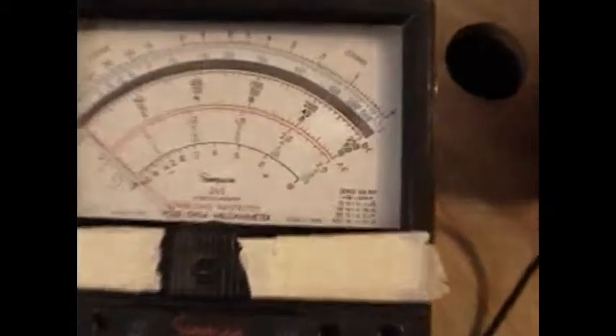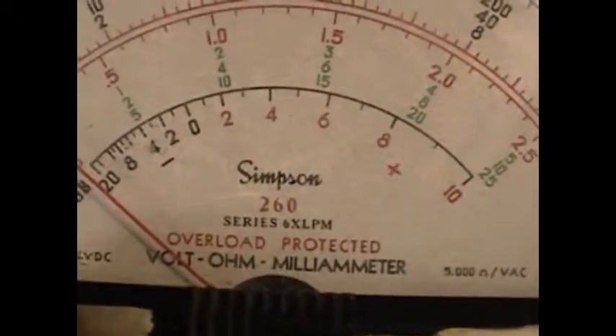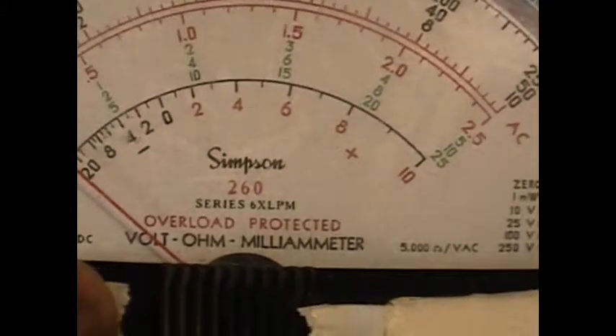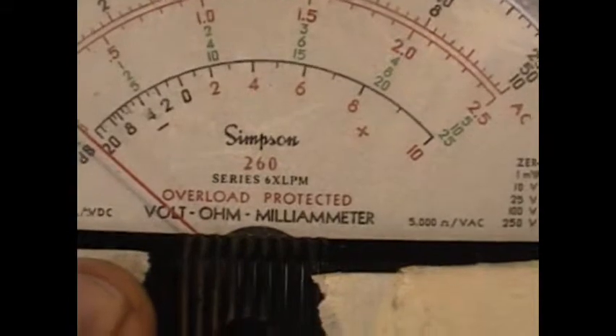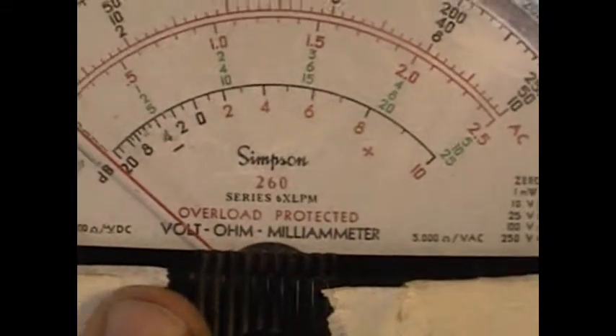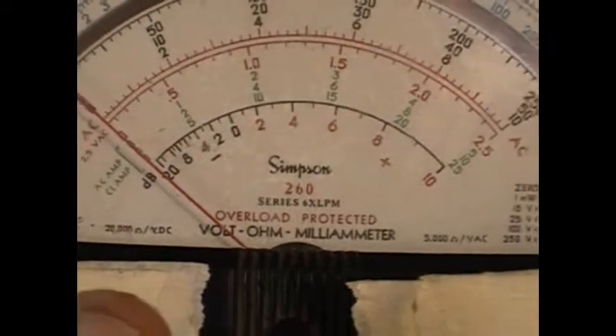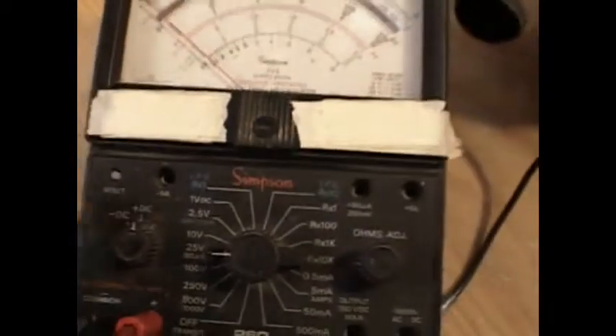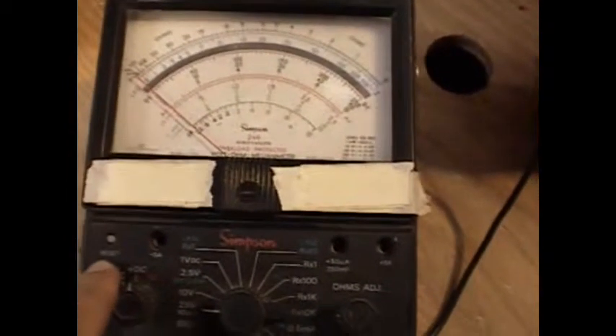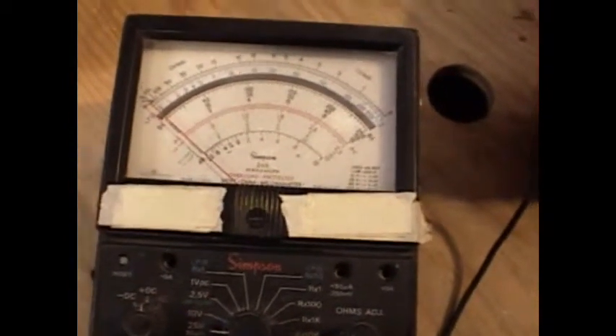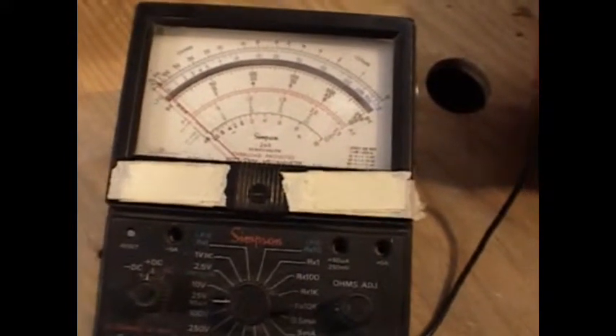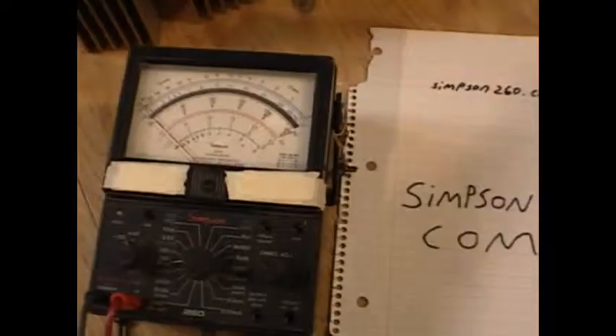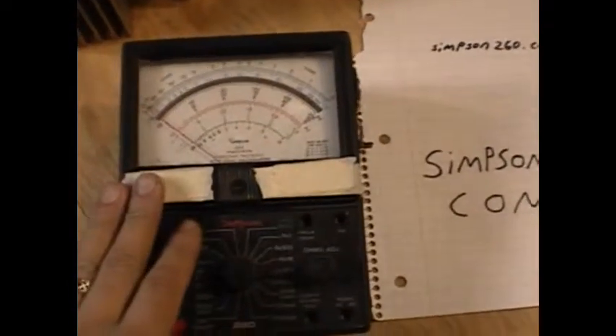The overload protection on this particular model. And once again, here if you look closely, you see series 6 XL PM. The key letter there that you should pay attention to is the P for protected. They have older models that are not protected. So the same measurements would have burned up one of the resistors in here, one of the low setting resistors. And that could change the whole measurement device, miscalibrating it, and you would have to have it replaced.